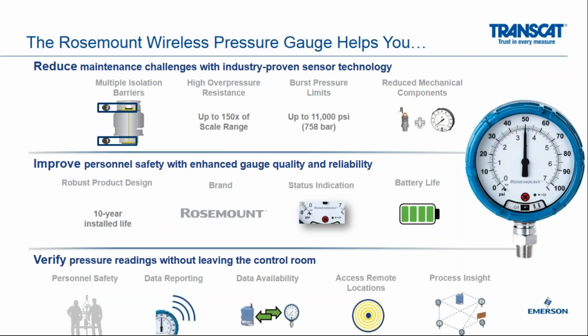In summary, what we have here is a pressure gauge that can reduce a lot of maintenance because the actual technology itself not only has multiple barriers, has incredible overpressure resistance and burst pressure limits, and it's reducing a lot of those mechanical components. The other piece here is you can improve personal safety. This is a 10-year life pressure gauge. You don't need to be replacing this gauge constantly.